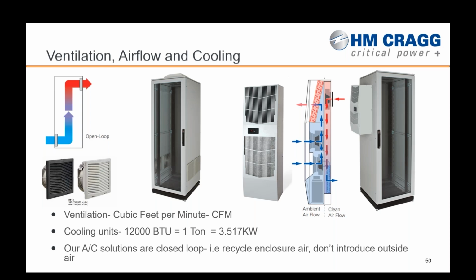We also have the closed loop system, more typical with our UPS and DC systems because we need that tight temperature tolerance. What's great about the closed loop system is it's constantly recirculating the interior air inside of these enclosures and not introducing any outdoor hot air or particulates that might be in the air. So if we're looking for a data center type environment for our equipment and placing that equipment in the opposite of a data center type environment, closed loop cooling is a great solution for that.